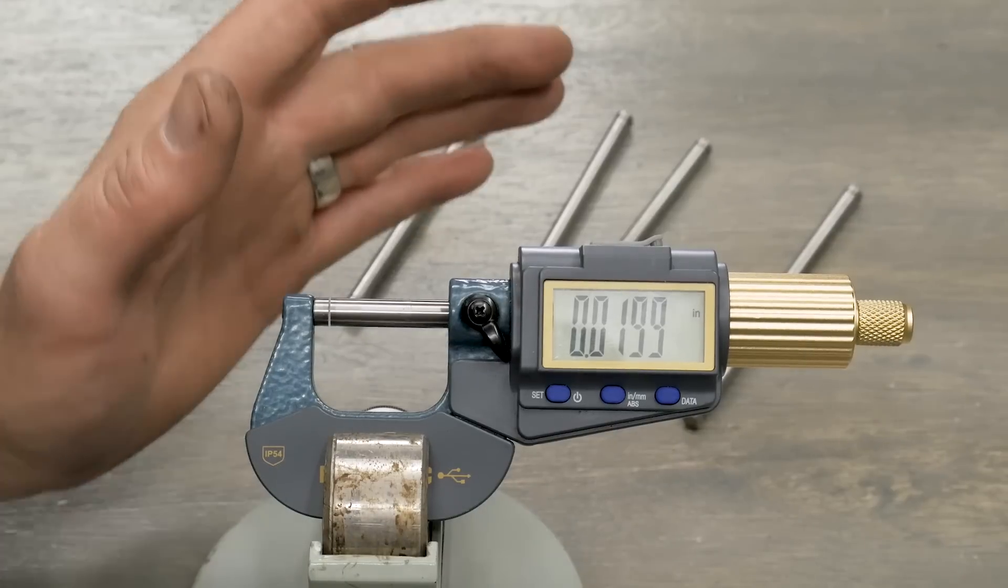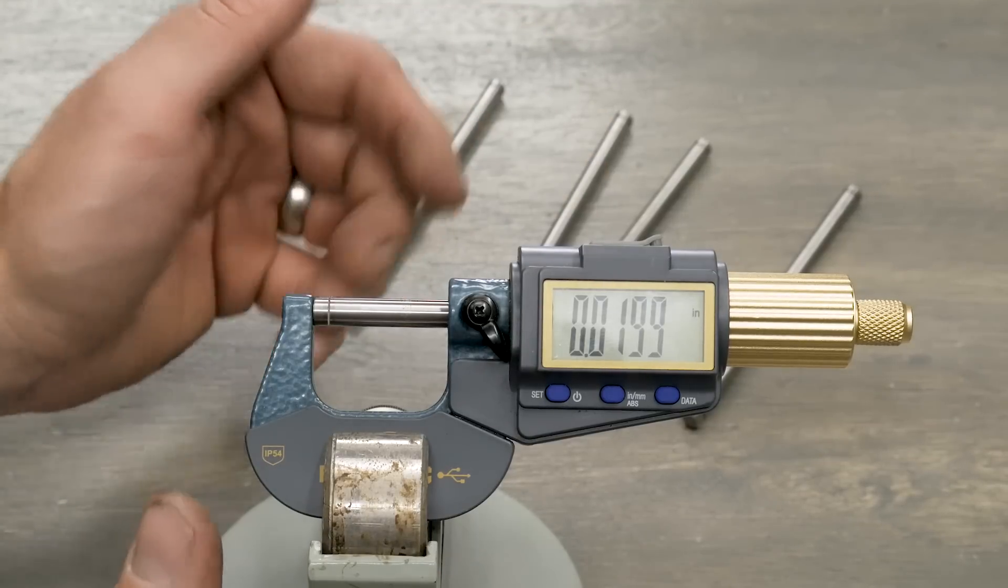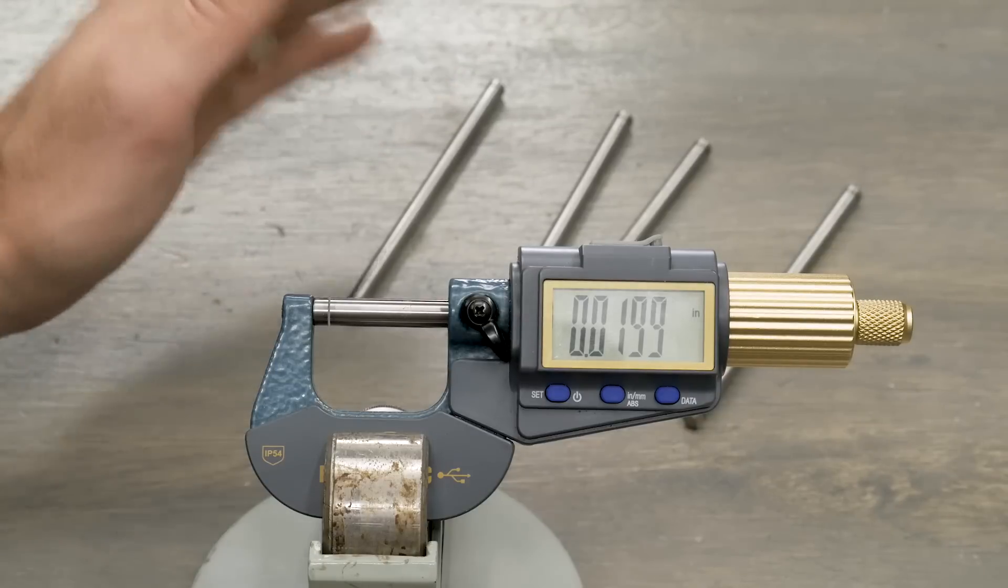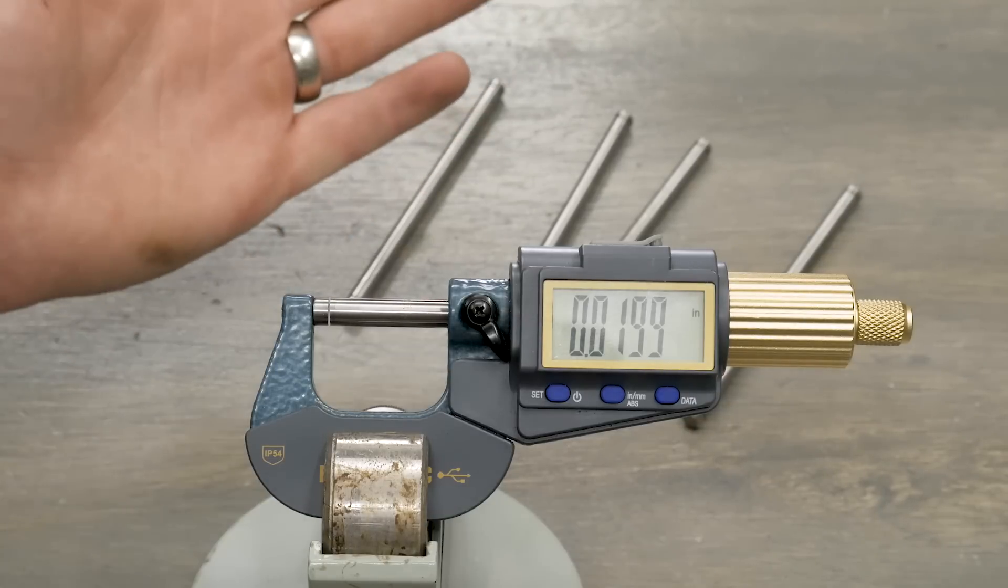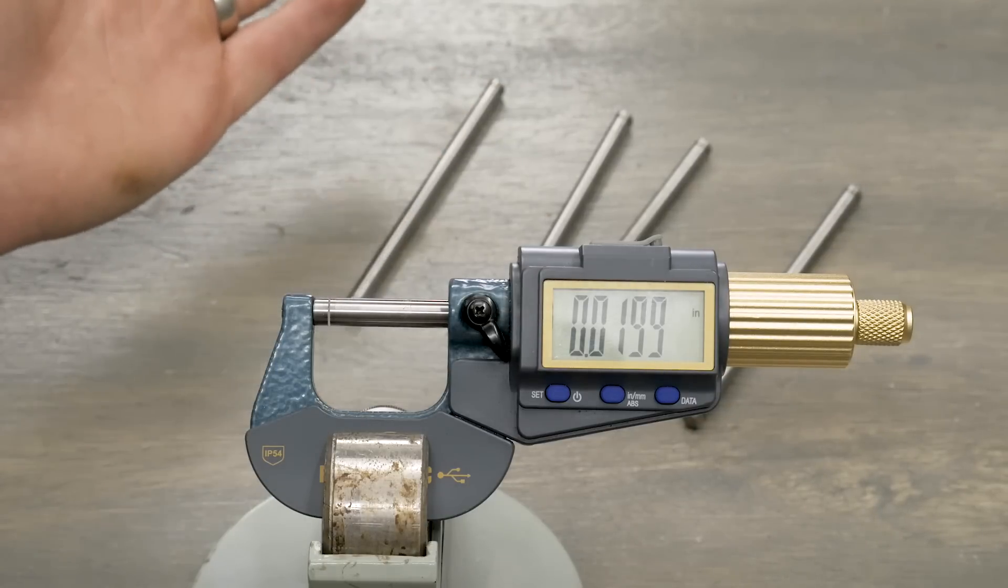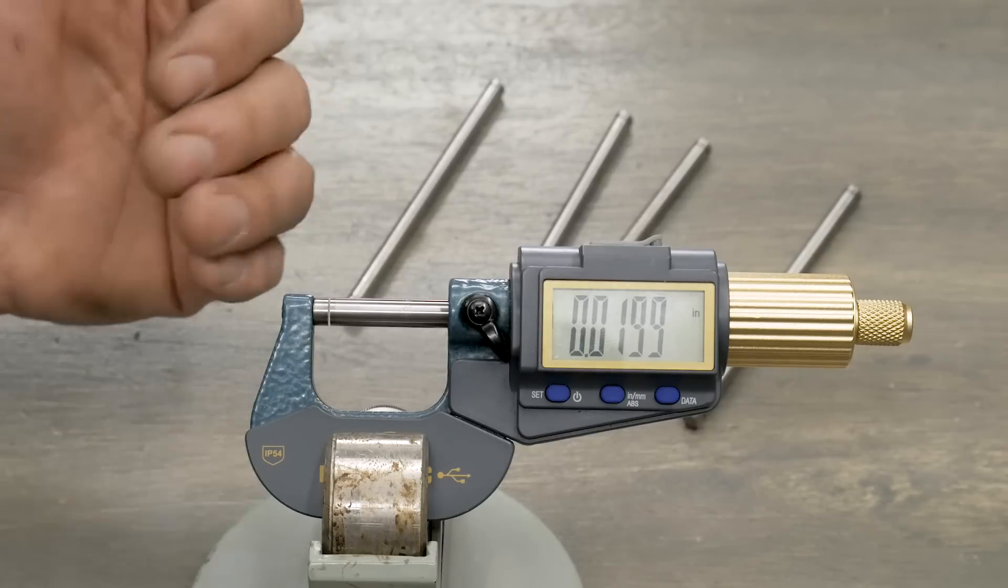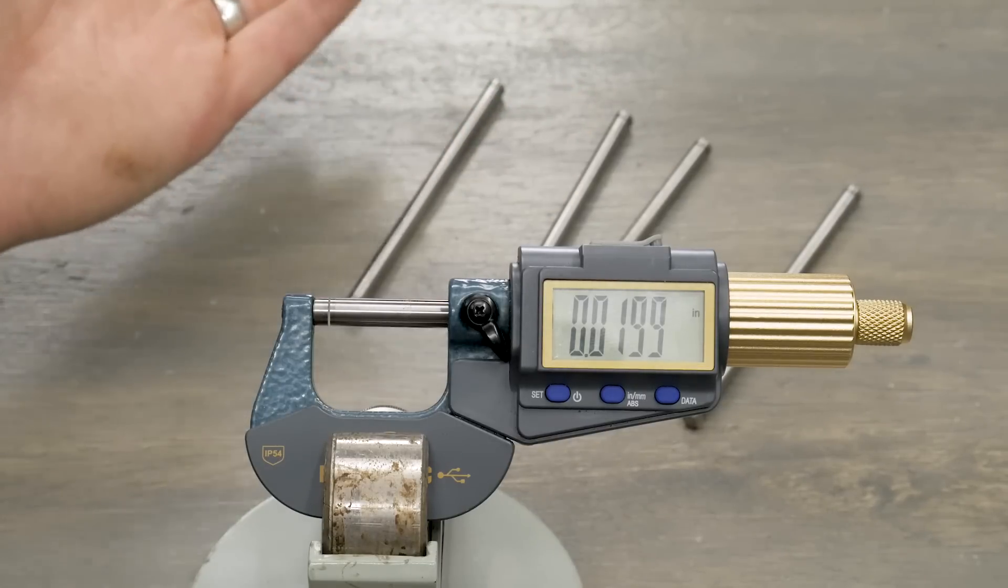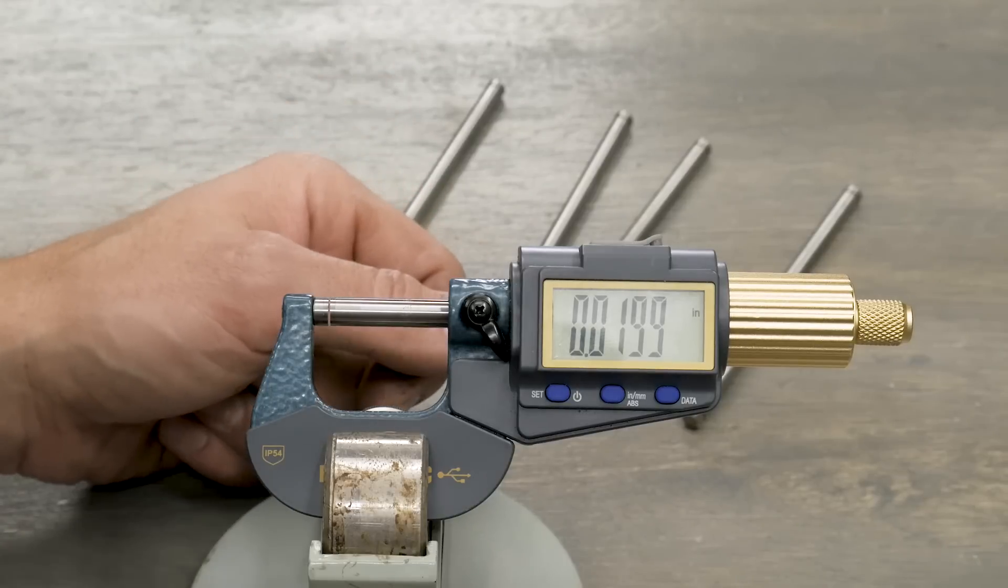Okay, so to demonstrate how this unit works, I've got it mounted in a stand here, and that's going to help me show you what's going on. I've got four quarter inch rods. These are precision rods, and we're going to take measurements of all four rods two different ways. First, we'll do absolute measurements that are the actual diameter, and then we'll do relative measurements, which will show us the difference between these rods in terms of diameter.